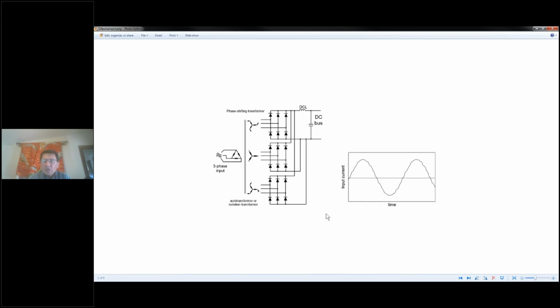I'm going to make a short comment on that. When we go to service and repair a drive that's been in the field for longer than its anticipated or designed service life, we have to make a decision. Are we really serving the best interest of the customer by repairing the part of the system that has failed? Or are we doing the customer a service to recommend replacement to state-of-the-art technology, giving him another 20-year run, if you will? And that's a decision that you have to make. I'm here to bring up the decisions. I'm not here to make them for you. This is an individual situation. It's up to the end customer ultimately. But the factors are significant.